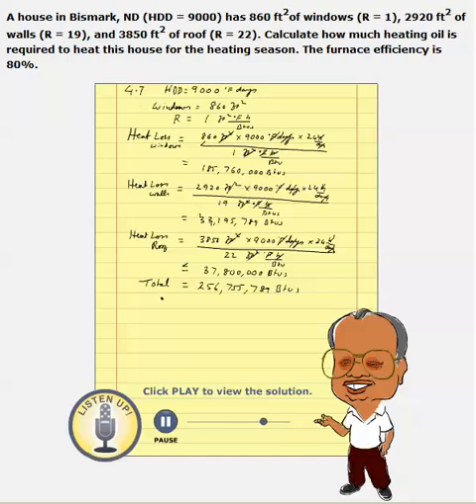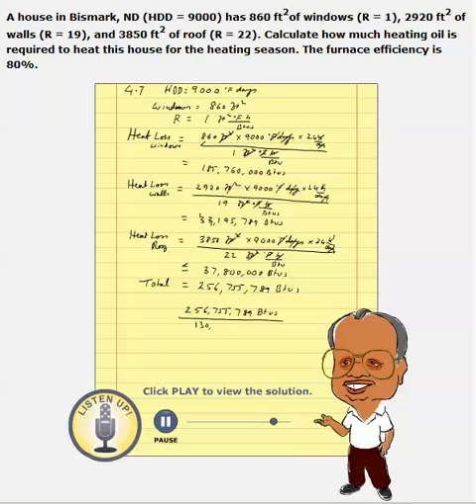The furnace efficiency is given, and we are using heating oil in this case. Heating oil provides 130,000 BTUs per gallon — so how much is required? We need 256,755,789 BTUs. When we buy heating oil, we get 130,000 BTUs for every gallon, but this is theoretical.